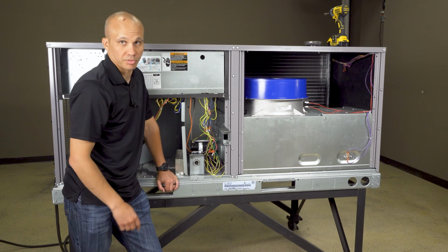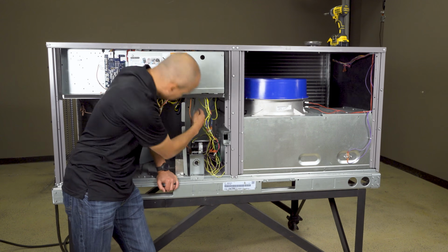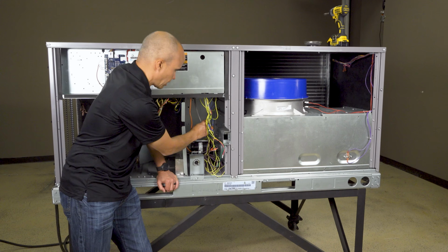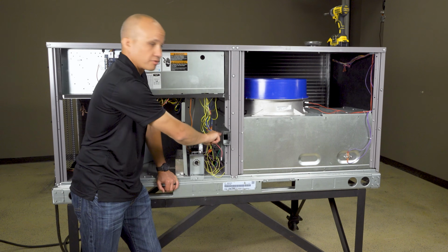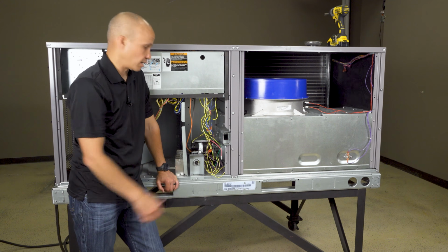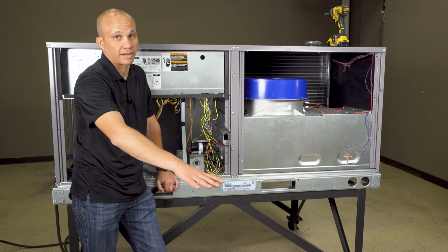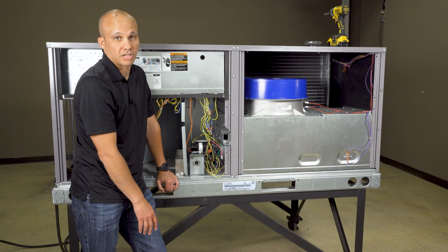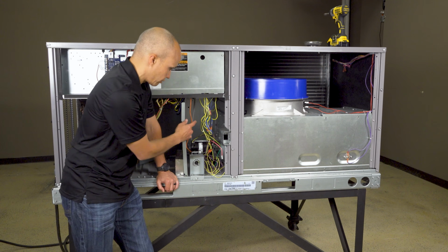And then we have some safety protections on here. Up inside here, we have a pressure switch, which is what these hoses are connected to. Or this hose right here, the gray one, is connected to. So if I'm not able to move air through this fan, because something's blocking it, a bird built a nest in here or whatever, that pressure switch is going to realize it and shut the whole thing down. We don't need to start making a fire inside the heat exchanger with no way to get rid of the products of combustion. So that's part of that pressure switch's job.